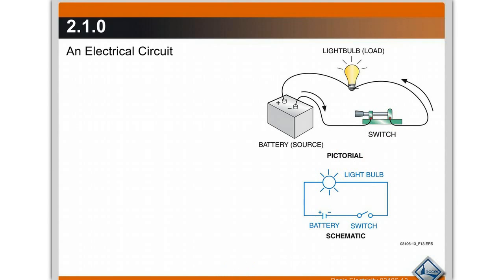Remember that all schematic diagrams, doesn't matter how big or how small, no power applied, the system is at rest, meaning no motors running, no fans running, no light bulbs on. It's just sitting there waiting for something to happen.